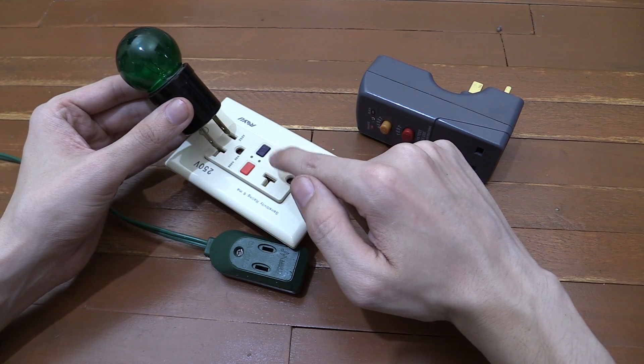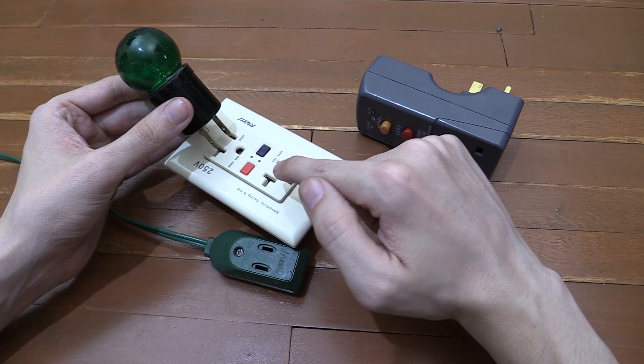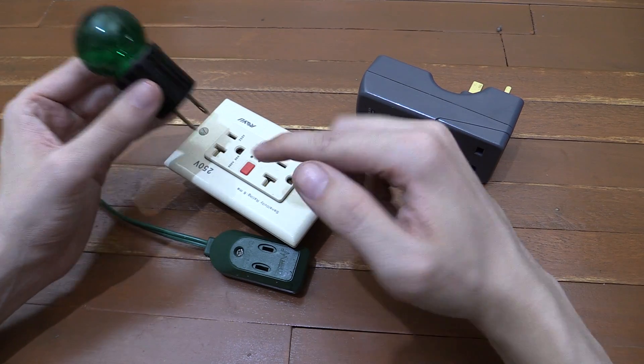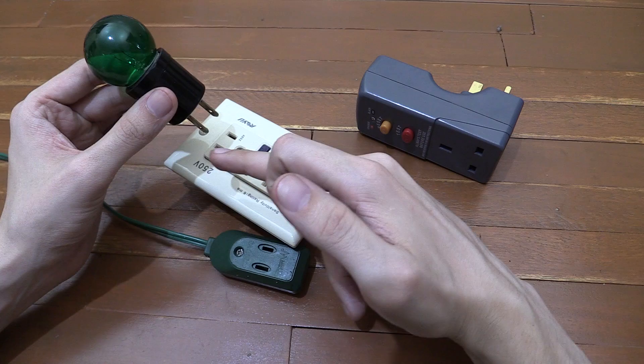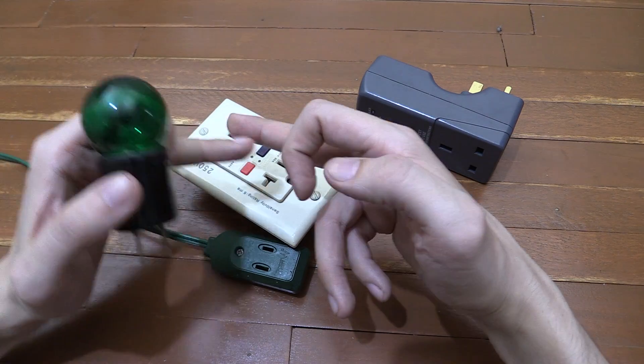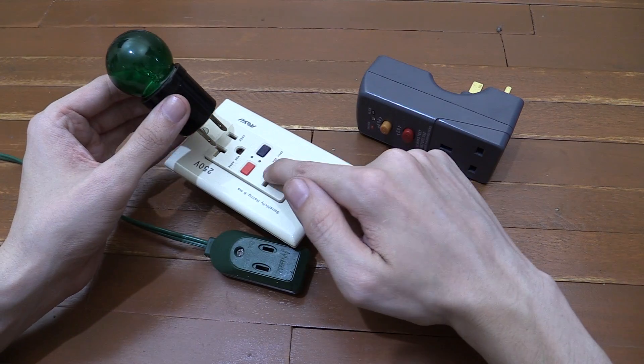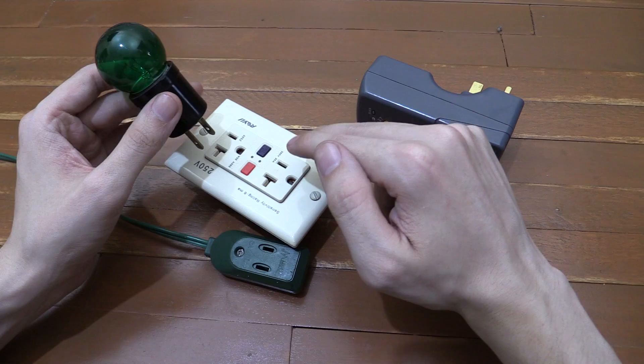So the way these work is they measure the current going out of the live and coming back to the neutral. If they don't match, they know that there's a fault somewhere, for instance you're touching it and the electricity is going through you to ground. So as soon as they sense that imbalance, they cut off the power immediately.